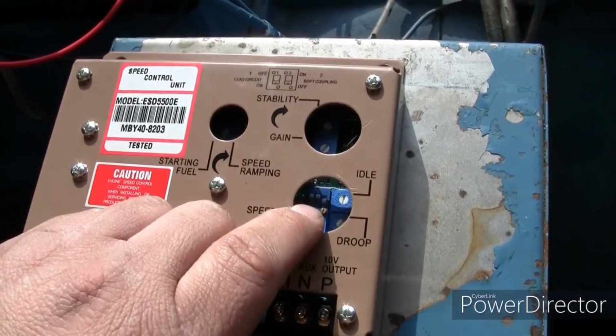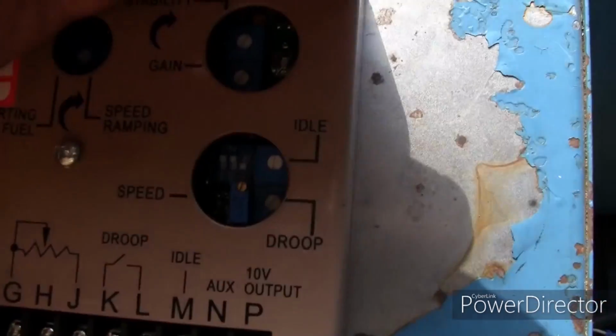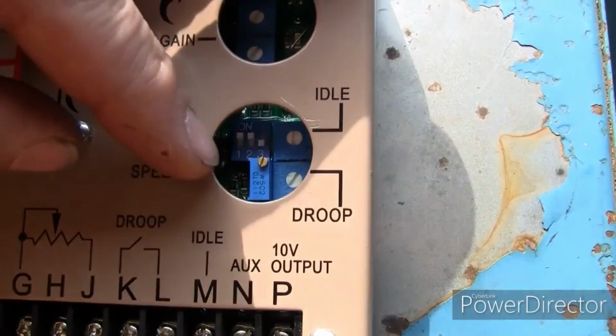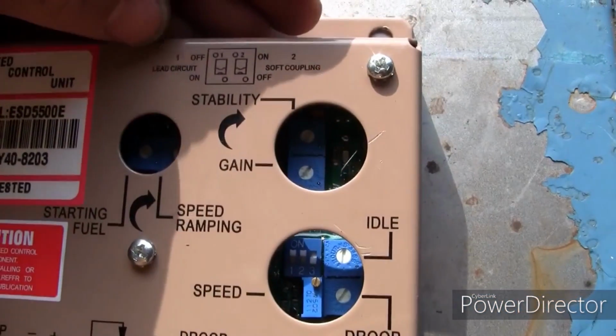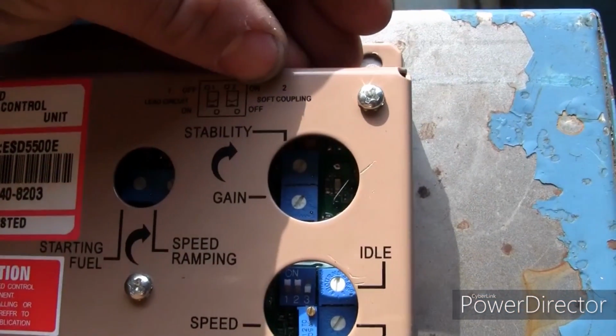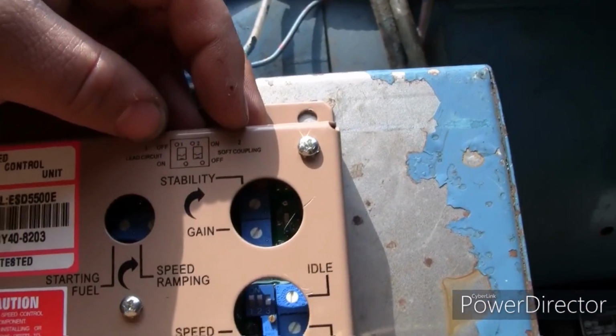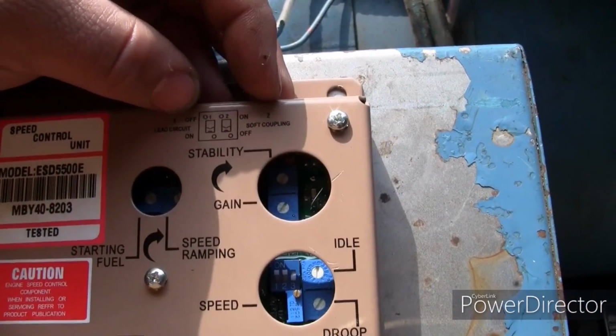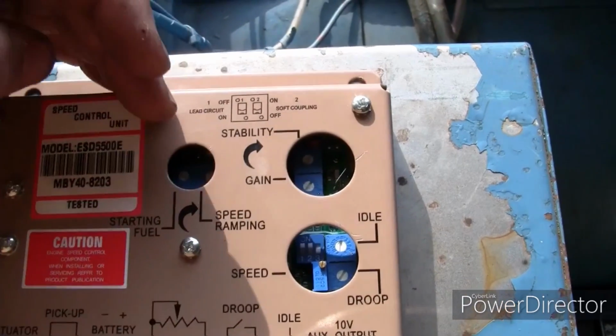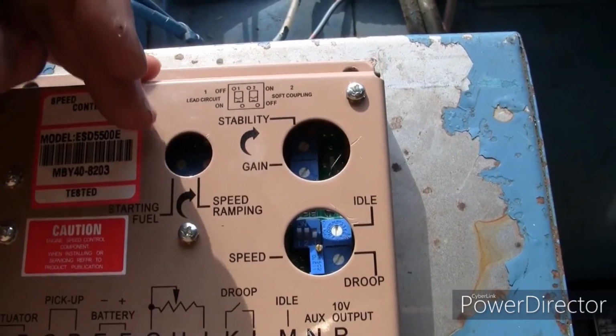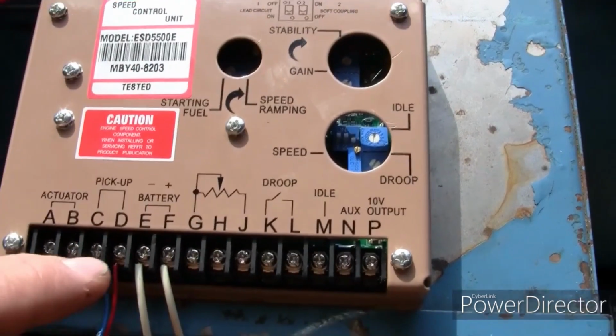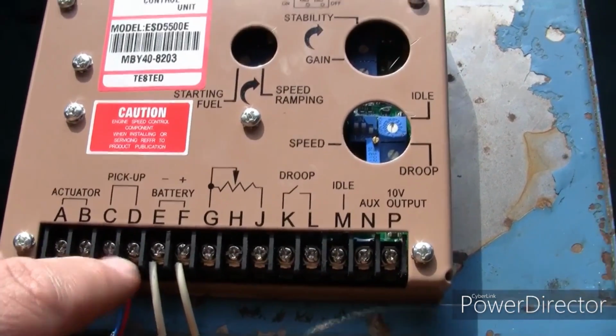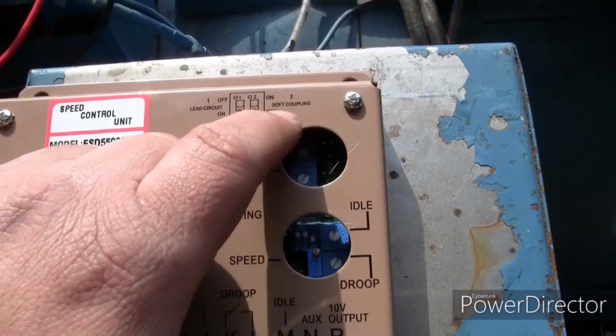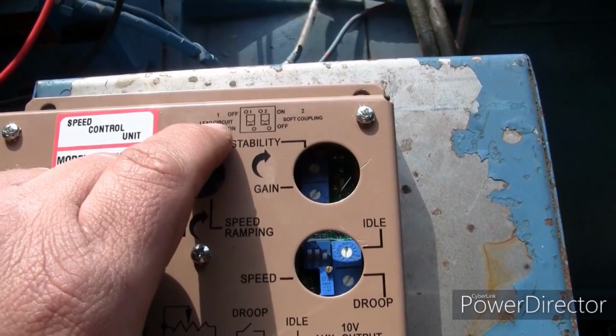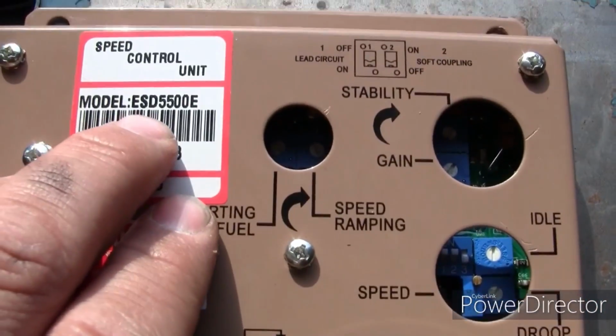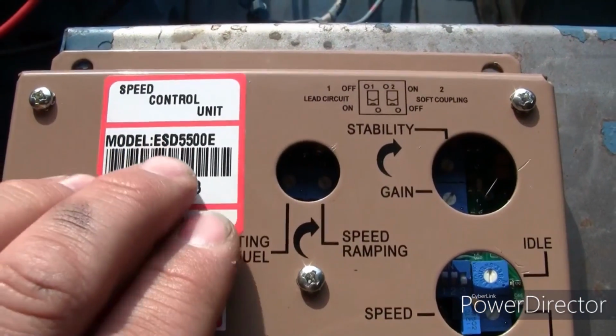These little dip switches here, right there, 1 and 2. Lead, they call that the lead circuit, and soft coupling. These are modifications on the way the governor responds to changes in the pickup signal. You can read about what soft coupling is and what the lead circuit is if you look up this model, the ESD 5500E, on the internet.